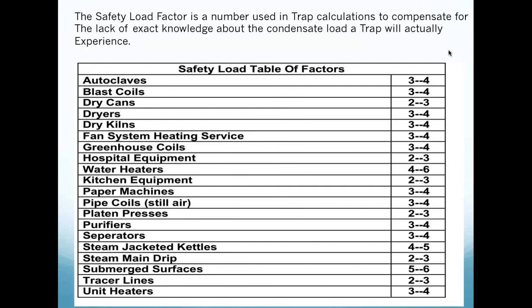And unfortunately, I have a couple sad stories where people have died because insulating contractors ended up taking insulation off during a work outage, and the condensate steam traps that were supposed to handle the condensate load were not able to handle it during the time that the piping insulation contractors had stripped it to renew the insulation, and unfortunately they had an event, and lost their lives.